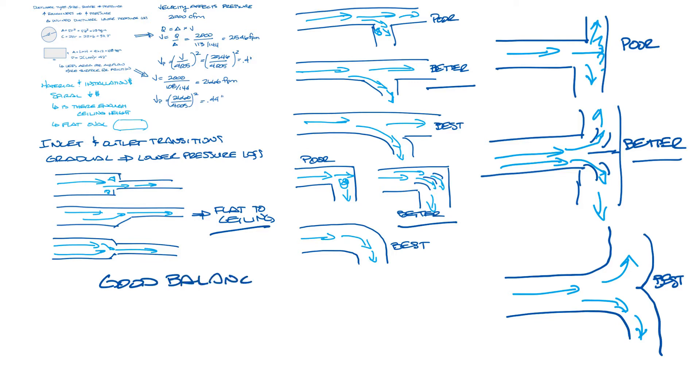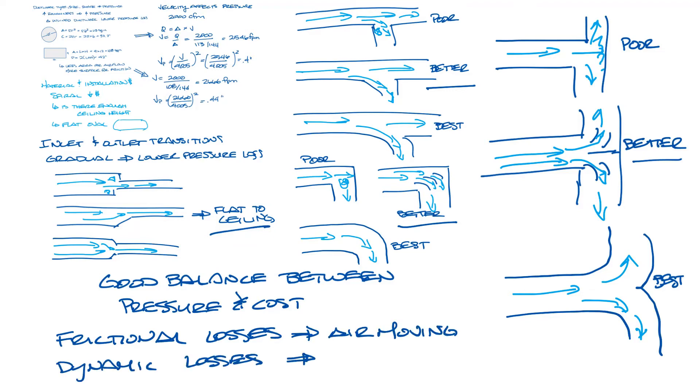You really want to have a good balance between pressure and cost. These different pressure losses fall into two categories: frictional losses caused by the air moving through the ductwork, and dynamic losses caused by disturbances to the air flow from changes in the area or direction.